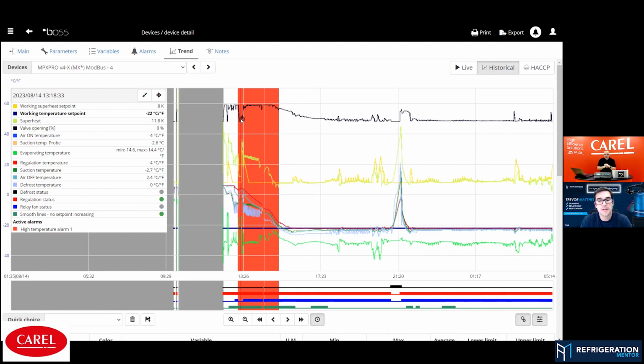What we are doing is, when we are close to the room temperature, to our set point, we start to manipulate our superheat. So the idea is to make the superheat higher the closer we are coming to the room temperature. So we will never reach a cut-out temperature. That's the idea, more or less. We can talk about this in one of the other CO2 Mondays. All of a sudden, I love it.